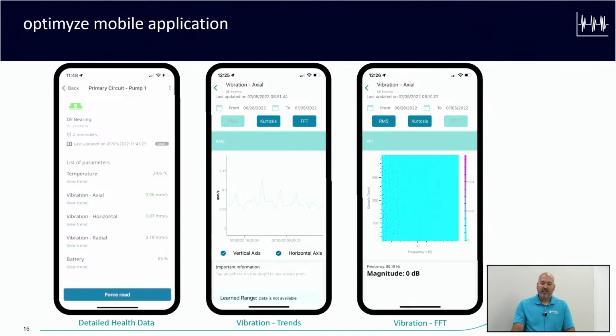The Optimyze sensor is going to create a blue bar essentially across the graph, just to let you know the normal operating range of that asset. So it's not going to necessarily trigger any alarms if you go outside that normal range, but with some manual intervention or interpretation, you might start to see vibration or temperature levels drift out of that blue bar, giving you even earlier warning indication that a potential problem may be happening or approaching.